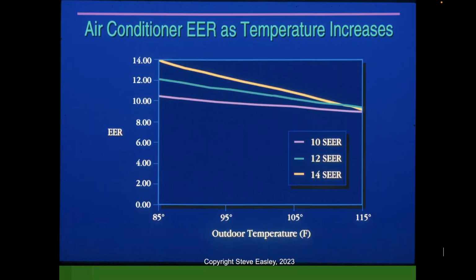Hold on a second. We have one question here. Chet wanted to know, can you estimate the temperature of heat pump heated air at the outlet versus gas hot air heat? Hold on, I'm going to show you some examples of that. I'm even going to show you one of my own examples from the heat pump that I have. So hold on, again, the discharge temperature is a function of the equipment efficiency and certainly the equipment capacity, but also the outdoor temperature to some extent. But that's changed with the cold climate heat pump. So it's kind of a complicated answer, but I'm going to get to that.